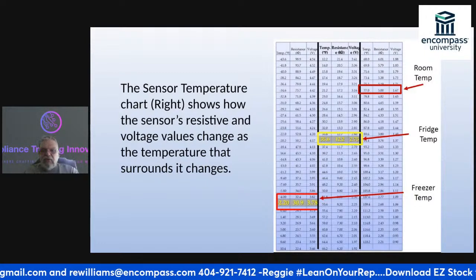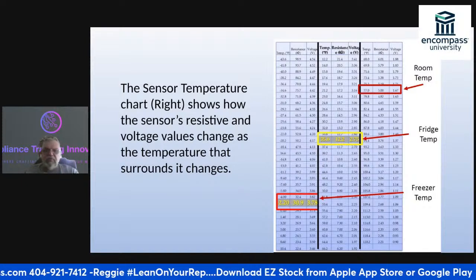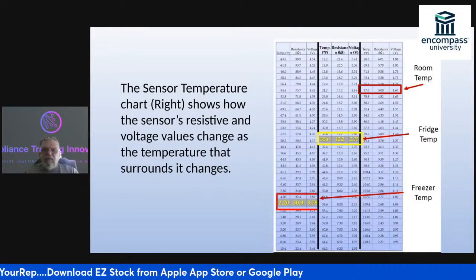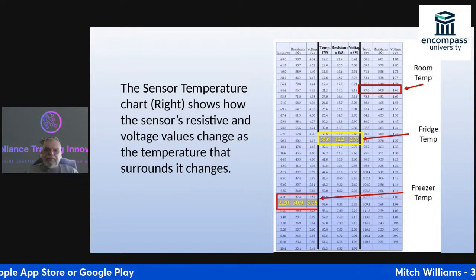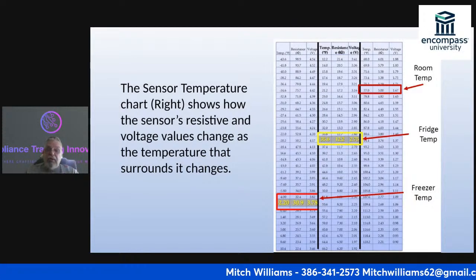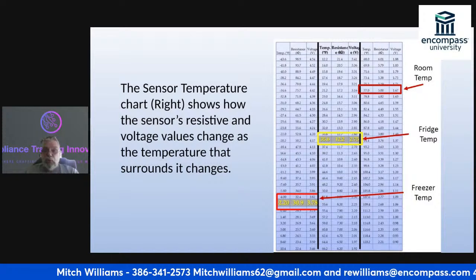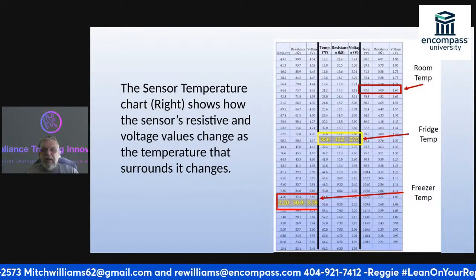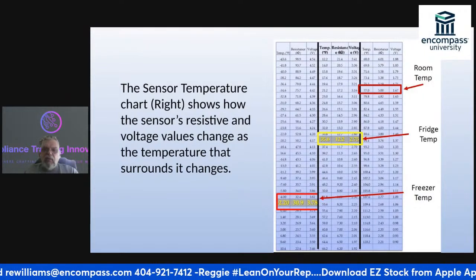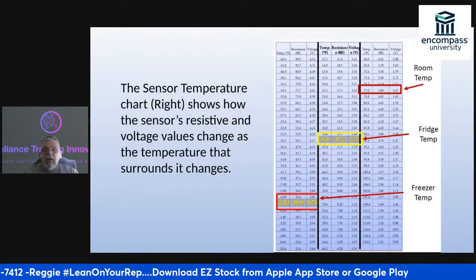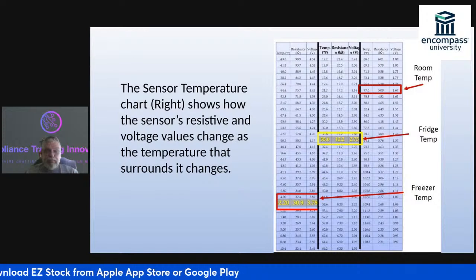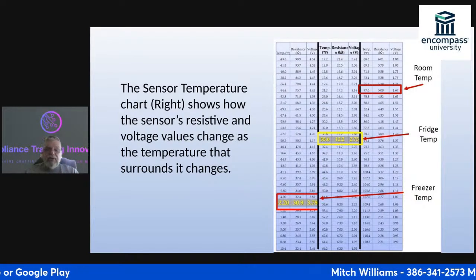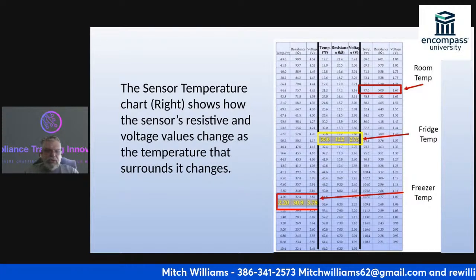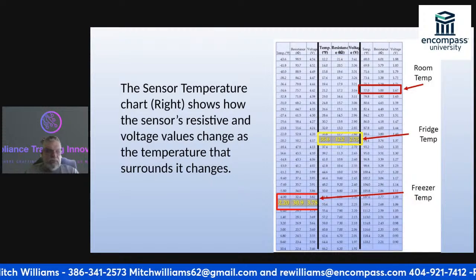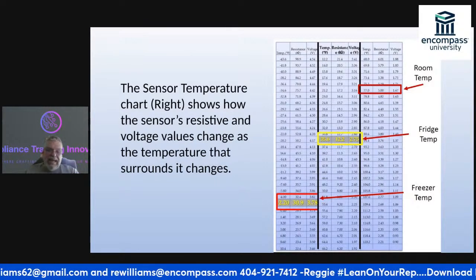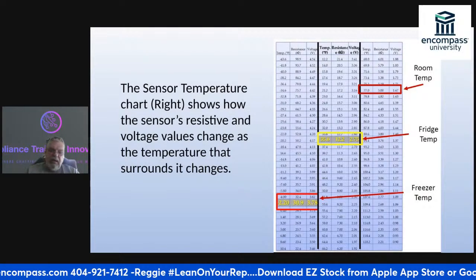The first thing that I check is at room temperature, which is about 77 degrees. I would get about 5.0 ohms of resistance. That's at about 77 degrees in a home. As that sensor cools down, you can see that at 35.6 degrees, I now have a resistance of 12.2 ohms. I'm getting about 2.75 volts. As it continues to cool down in the freezer section, and I get down to about a 2.2 degree temperature, I'm going to have 30.9 ohms, or I'm going to read about 3.78 volts.